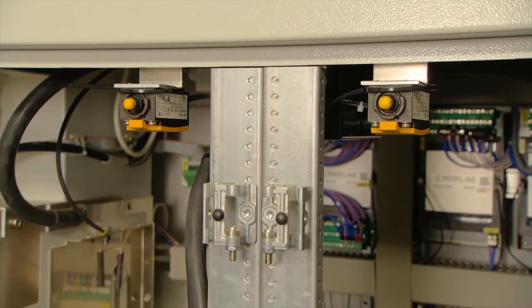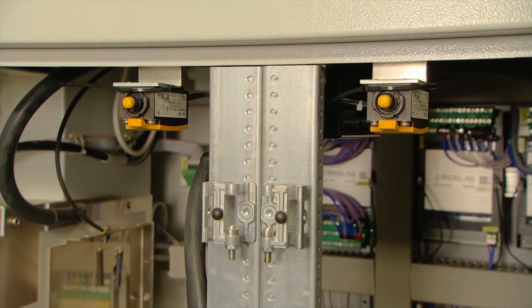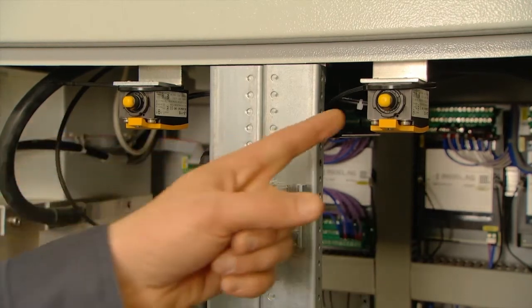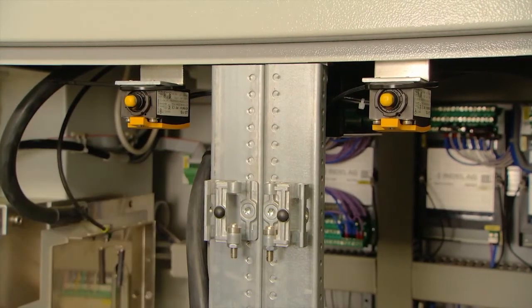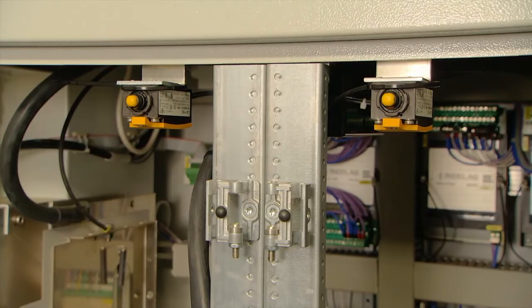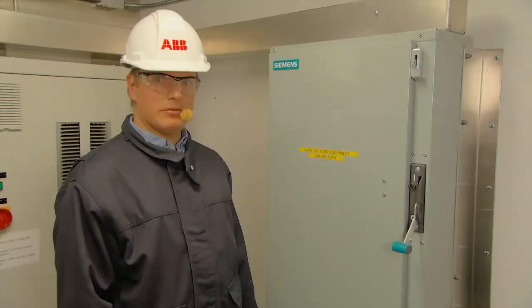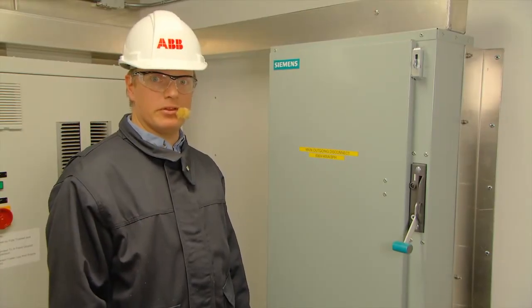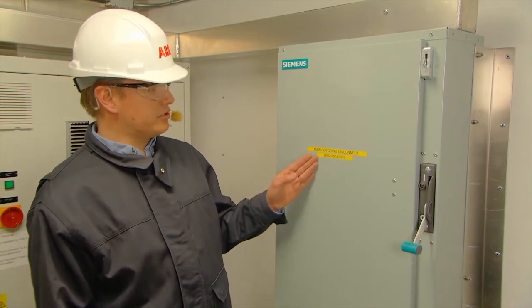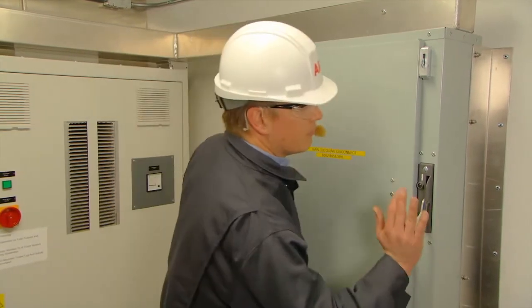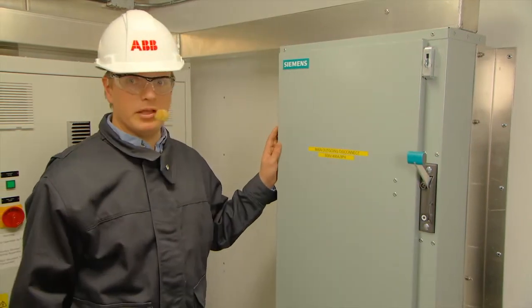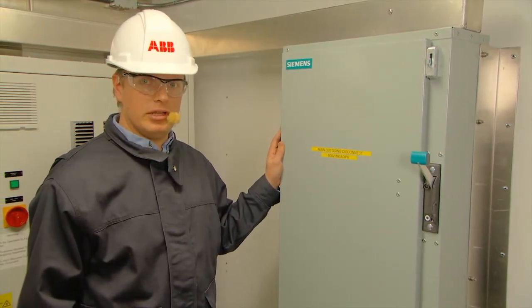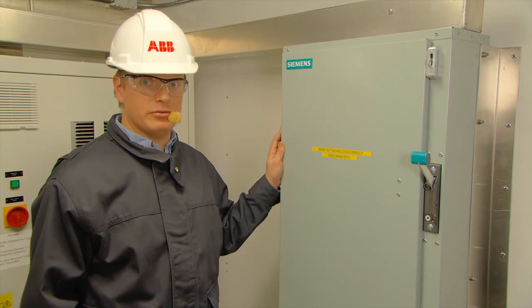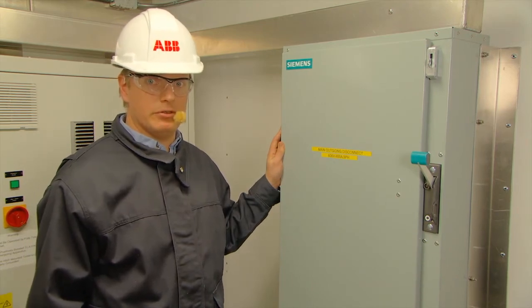To prevent the converter from running when the doors are open, there are 2 switches, one for each door, which will stop the converter whenever the doors are opened. Between the converter and the transformer that we're going to dry, there is a safety switch. This disconnect switch has to be closed when the plant is supposed to run. And when you're leaving the plant, please open the switch to ensure that no current is injected to the transformer.